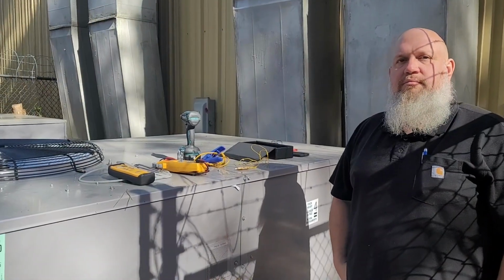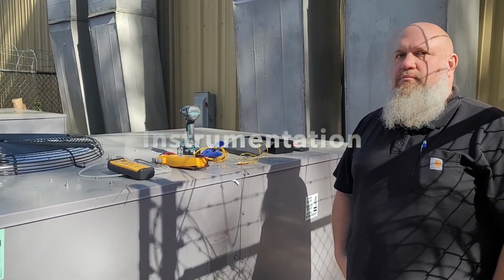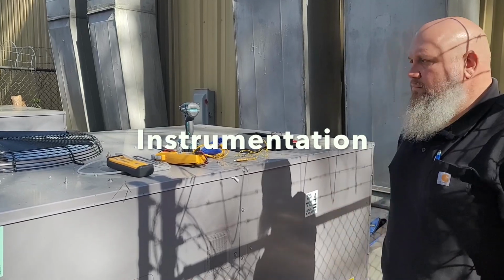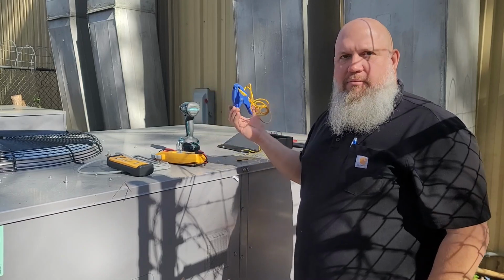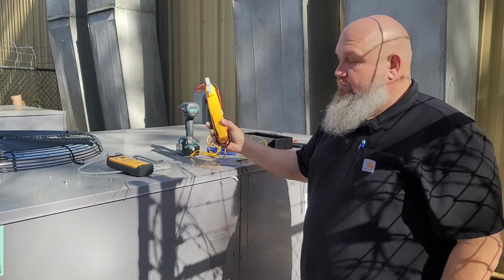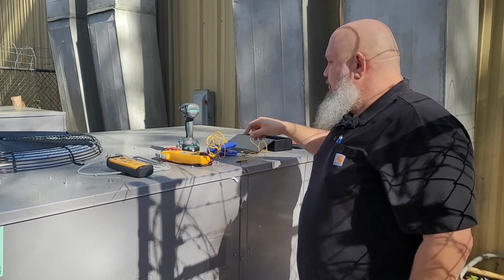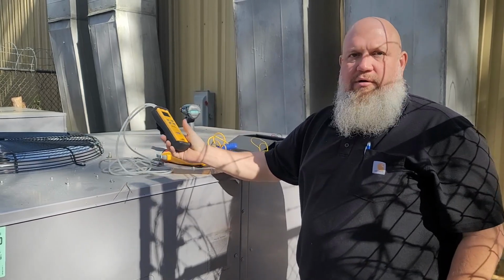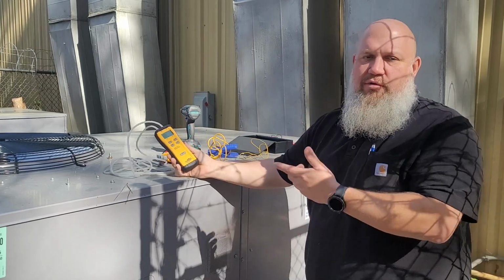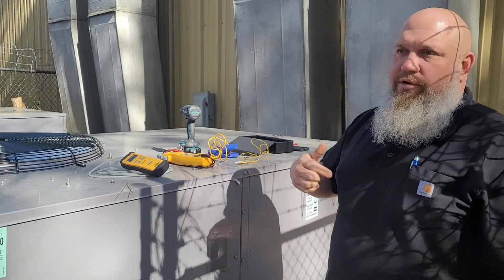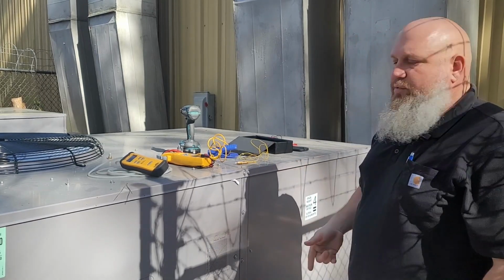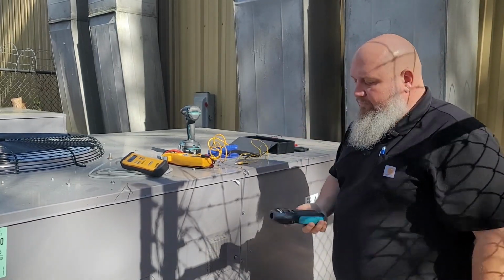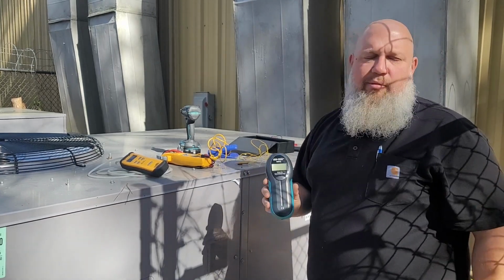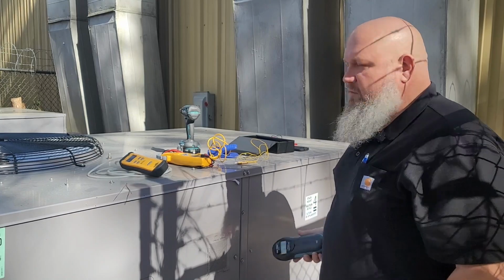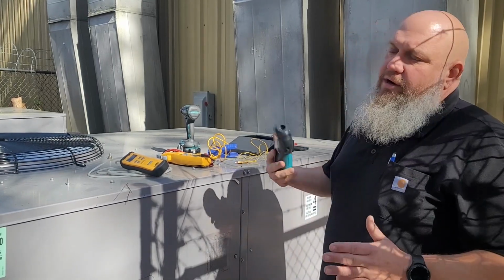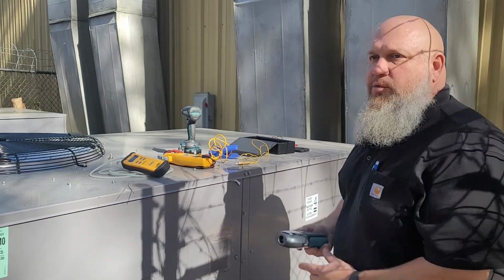Before we get started taking the performance measurements, tell us a little bit about the instruments you're using today, and what measurements will you be taking? First, you need a good pipe clamp for your temperature and a meter that will read the pipe clamp. Of course, you need a manometer. I use a dual port because it gives me real-time readings for both of them, and that's for your static pressure and your TESP. Then you've got a digital optical tachometer, so you can do your RPM of your blower motor and blower wheel to make sure that your speed is set properly on the blower motor.